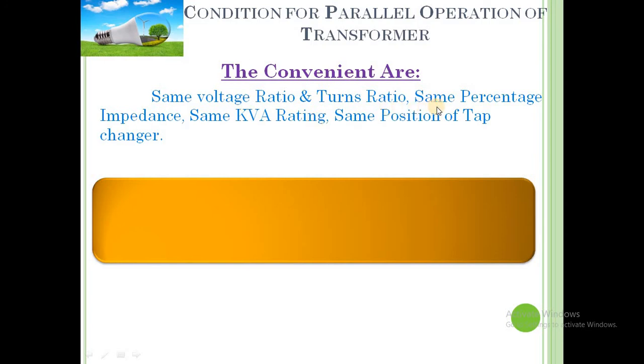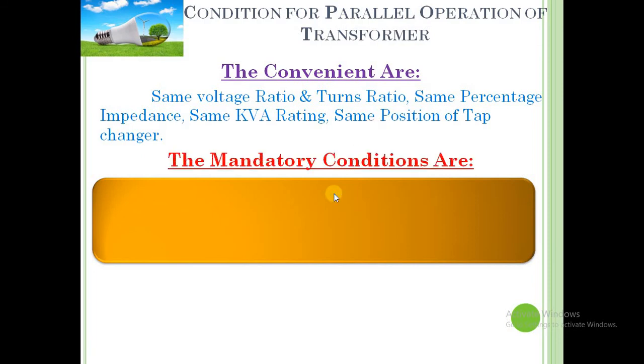It will not hamper too much on parallel operation: same percentage impedance, same kVA rating, same position of tap changer. So all these conditions, if not satisfied, then it's okay, the transformer parallel operation will be done. But some of the mandatory conditions must be fulfilled before connecting two transformers in parallel.